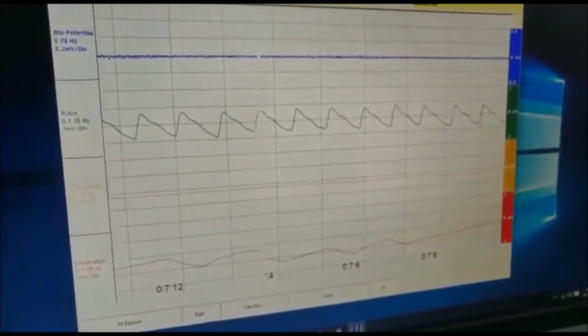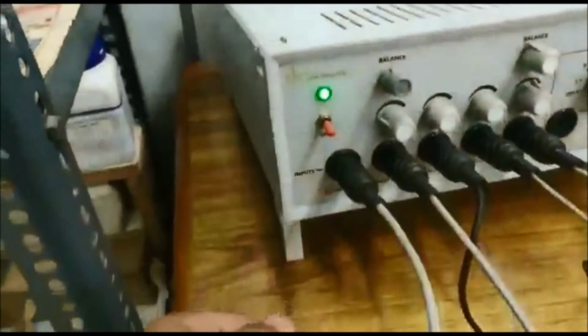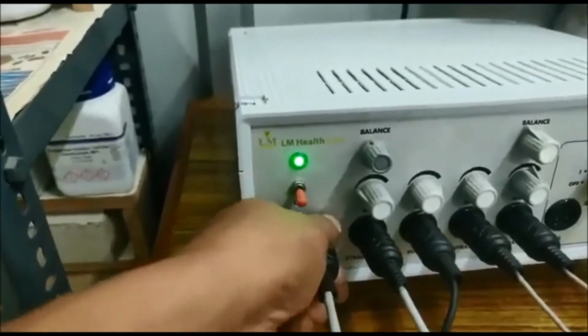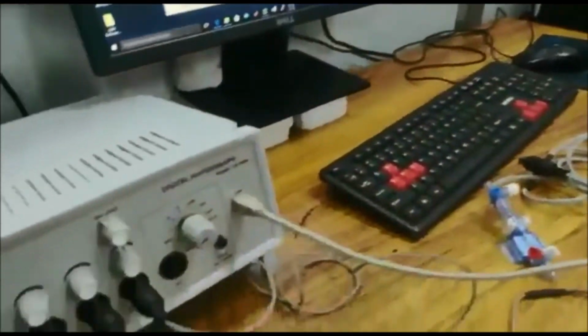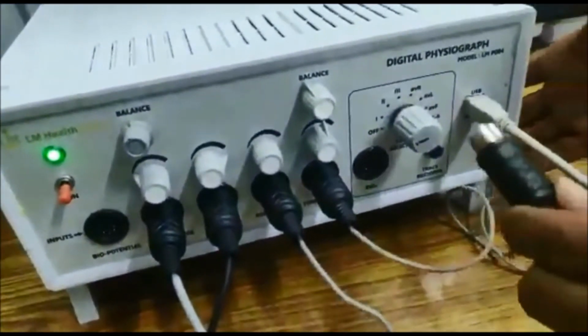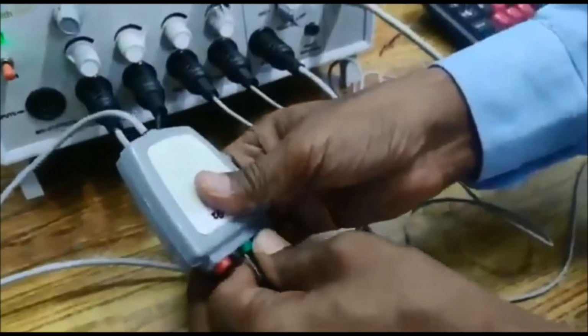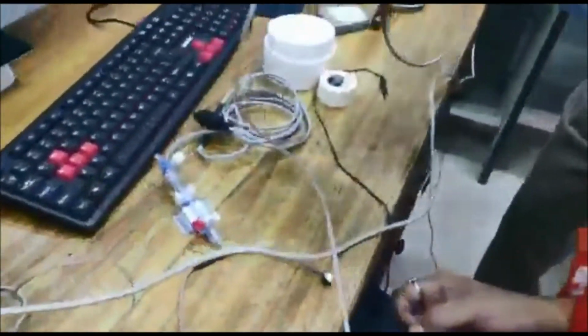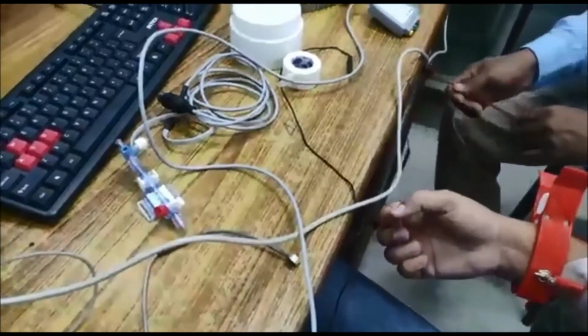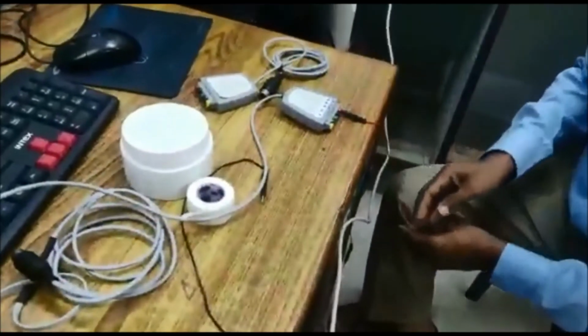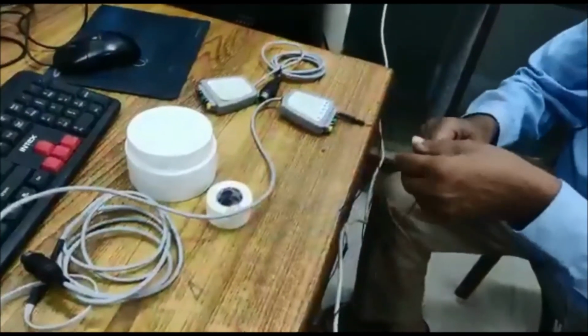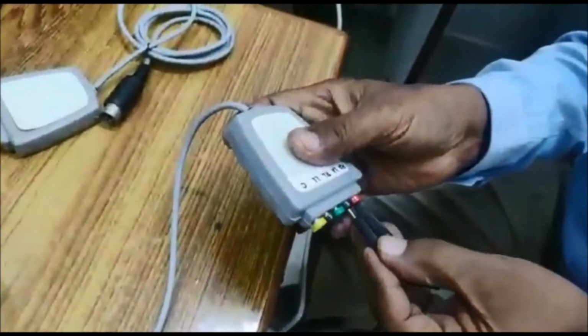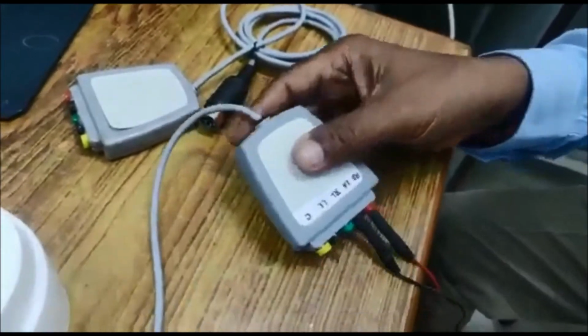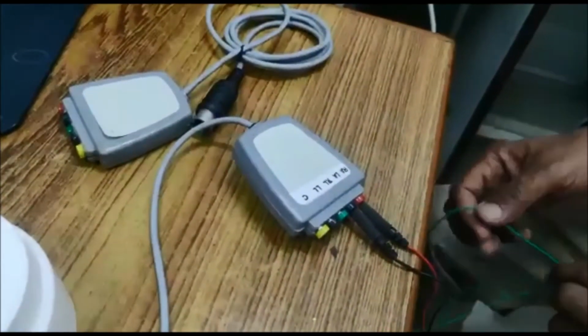And now we'll look at the EKG signal. So we'll remove this junction box from the biopotential input, and we will connect it to the EKG. We'll remove the biopotential electrodes and connect the clamp electrodes. The clamp electrodes are already attached to the patient. We just have to connect the respective electrode to the junction box. As you can see, first we are connecting the right arm, then the left arm. Now we are connecting the right leg, then the left leg.